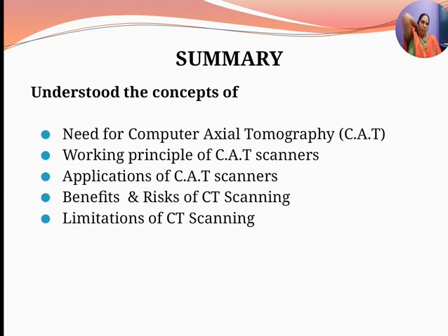Then the microcomputer senses the position of the X-ray tube and samples the output of the detector along a diameter opposite to the X-ray tube. Then, based on the calculations, the data obtained from a complete scan is processed by the computer. The output unit then produces a visual image of the transverse plane cross section of the patient. The camera is used to produce a hard copy of the record. Present day CT machines can obtain slices in 1 to 2 seconds in high resolution or 5 to 10 seconds in precision mode.